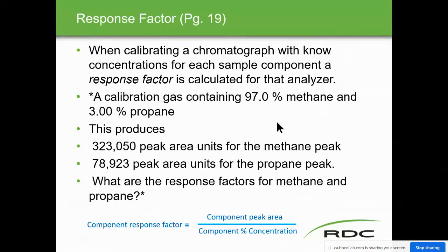The component response factor formula is not on the formula sheet, so write it down: component response factor = component peak area ÷ concentration of the component. For methane: 323,050 ÷ 97% = 3,330.41. For propane: 78,923 ÷ 3% = 26,307.67. These response factors are unique to each individual analyzer because every analyzer responds differently to each component.